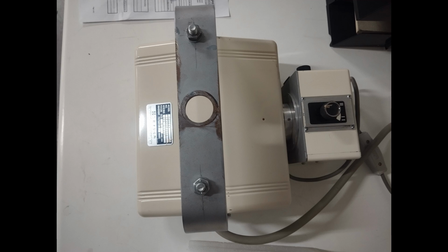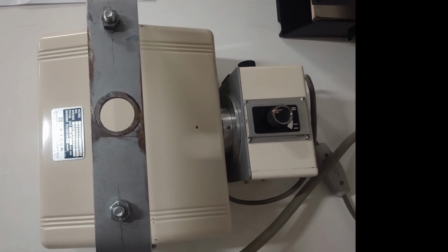Next, we have the X-ray source. This source does not produce any X-rays if there is no power applied to it. It is not an isotope and is artificially generated. This allows us to finely control the exact amount of X-ray radiation that is being produced, so we can get the ultimate image with the least X-ray dose to the patient.